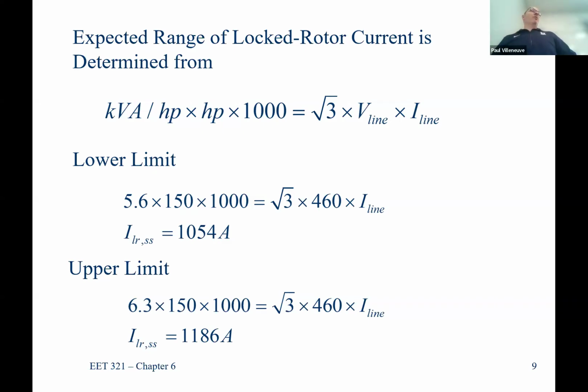We said an induction motor is a rotating transformer, right? So you have the same issues with transformers. They have an inrush current, just like induction motors do. But there's no usual kVA, just some standard ratings that we use. So we got to design our protection system for these values.